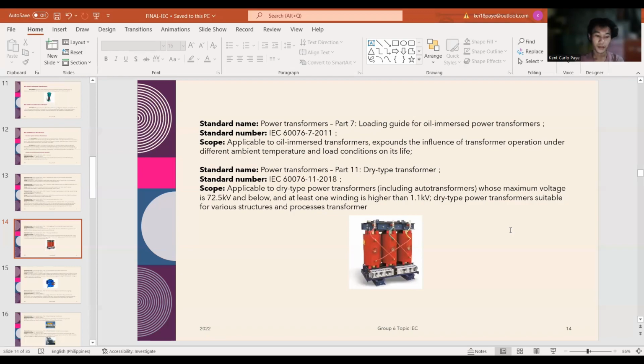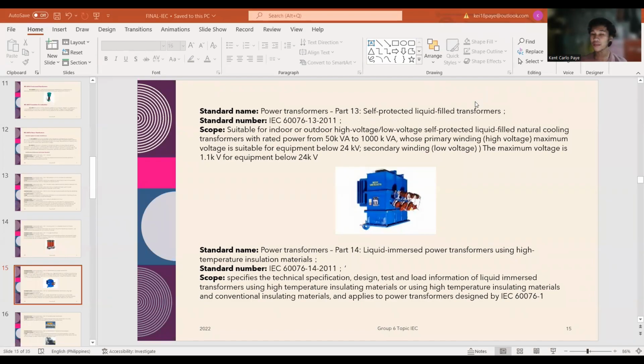Then also, this parameter standard provides guidance on service conditions, rating requirements, tappings, connections, ability to withstand short circuit, rating plate, temperature rise limits, insulation levels, climatic, environmental, and fire behavior classes that facilitate the cost-effective setup of dry-type transformers and long life due to low thermal and dielectric heating. It also allows users to develop and assist pollution-free and sustainable dry-type transformers and ensure the safety, performance, and longevity in transformer applications. And the next part of the 60076 parameter standard is the self-protected liquid-filled transformer.